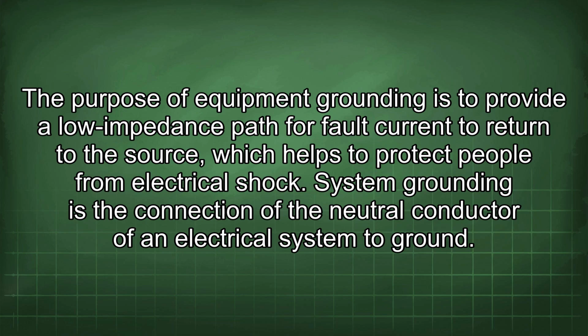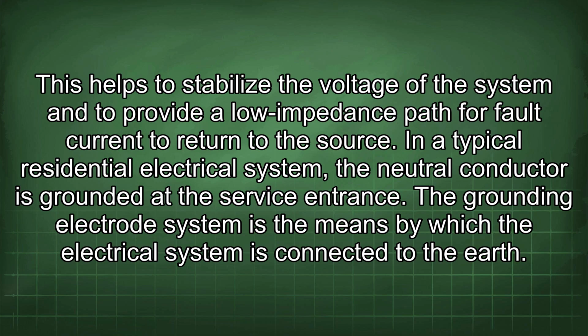System grounding is the connection of the neutral conductor of an electrical system to ground. This helps to stabilize the voltage of the system and to provide a low impedance path for fault current to return to the source. In a typical residential electrical system, the neutral conductor is grounded at the service entrance.